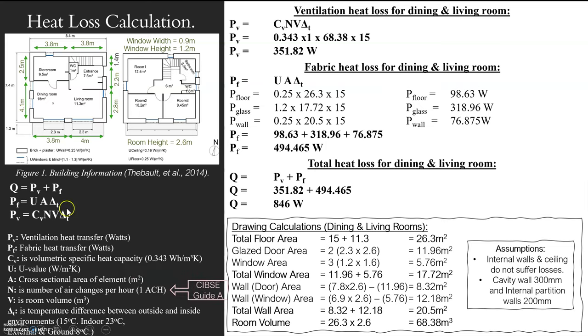N is number of air changes per hour — that goes back to our ventilation. When we're looking at how much heat is lost through ventilation, we need to know how many times that room is getting replaced with air — how many times does that whole space get its air changed? CIBSE — the Chartered Institution of Building Services Engineers — they say that for a living room situation, you need the air to change once per hour. So one air change per hour — that's the value there.